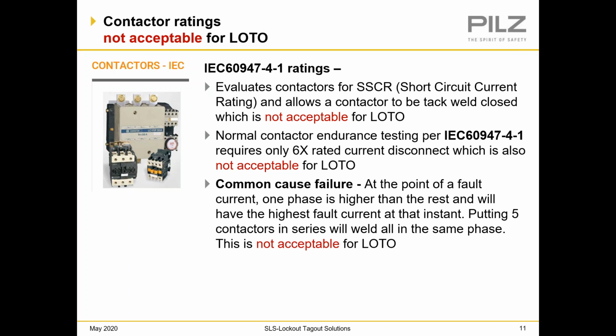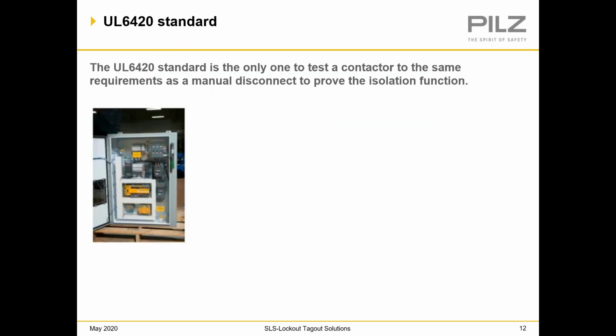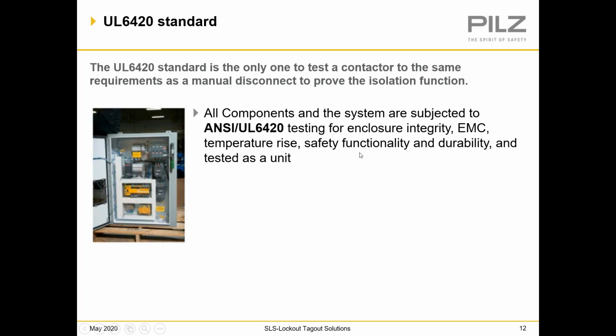In common cause failure, at the point of a fault current, one phase is higher than the rest and will have the highest fault current at that instant. So for instance, putting 5 contactors in series will weld all in the same phase, and that is also not acceptable for lockout. So the UL 6420 standard is defined as follows. First of all, the UL 6420 standard is the only one to test a contactor to the same requirements as a manual disconnect to prove the isolation function.